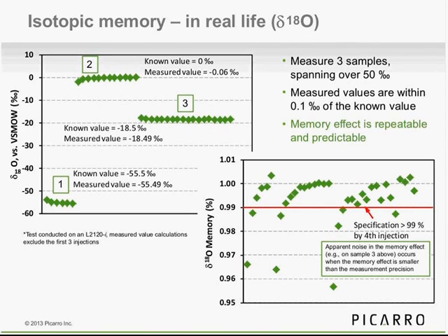You'll also notice that for the 3rd water type here on the memory scale, there's actually a lot of scatter here. And what this actually means is that memory isn't winning, precision is winning. So what I mean by that is that you've overcome the memory effect, so there's some noise in the measurement that's not related to memory.